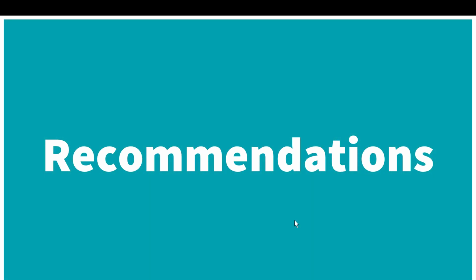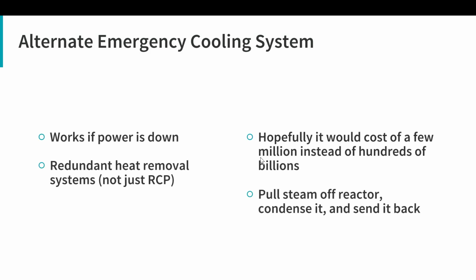So how would we have done things a little differently? Their main problem, it seems, was from a design perspective. There are a lot of reports that nitpick about this action and that action that they took on the day, but really their main thing was they were trying to use reactor coolant pumps to remove decay heat. And you really need something redundant if you want to guarantee safety, because even if it's not a tsunami, you never know if a system is going to fail. So we were trying to design something that works if the power is down and is redundant, and hopefully it'll cost a few million instead of the hundreds of billions of dollars that it's going to cost to clean this up. So we thought, hey, we can just pull the steam off the reactor, condense it, and send it back.